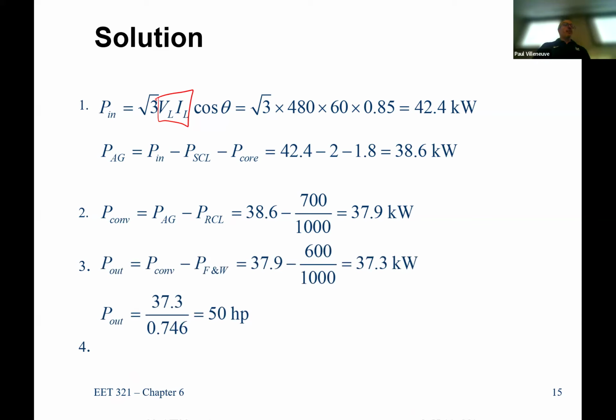Now I got to start dumping out any friction and windage losses and any stray losses that are there. So I take out my stray losses or friction and windage losses. Now I'm down to 37.3. And interestingly enough, remember how I said I didn't need that 50 horsepower? It just so happens, though, that that happens to be 50 horsepower when it's drawing 60 amps. That's coincidence. Doesn't actually have to draw 50 horsepower. It's just that operating at 60 amps gives you that.